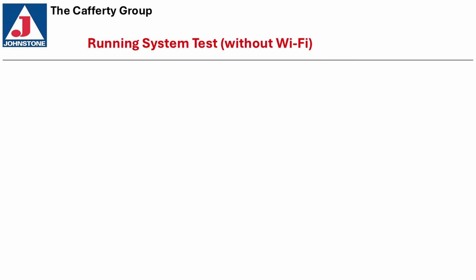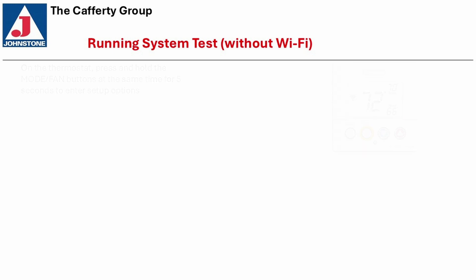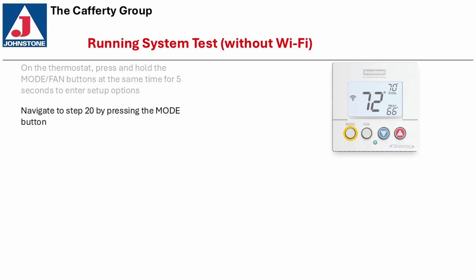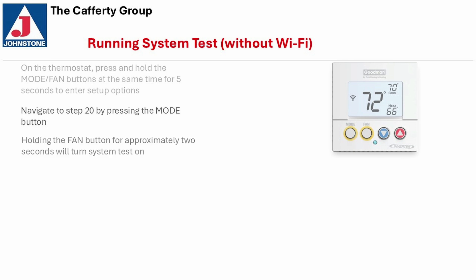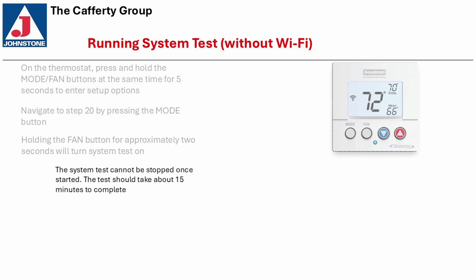Running System Test Without Wi-Fi: on the thermostat, press and hold the mode and fan buttons at the same time for 5 seconds to enter setup options. Navigate to step 20 by pushing the mode button. Holding the fan button for approximately 2 seconds will turn the system test on. The system test cannot be stopped once it's started. The test should take about 15 minutes to complete.